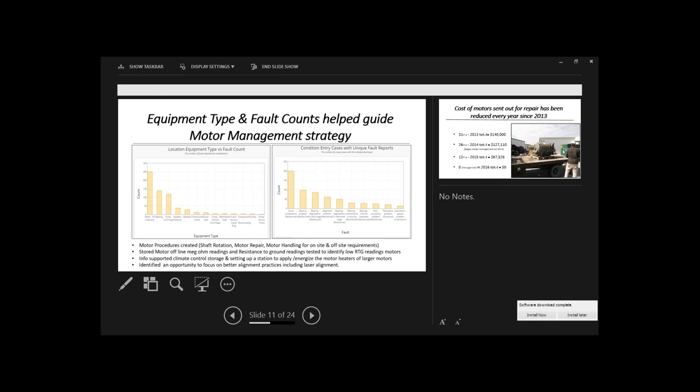In addition to that, he's gone a step further and he does a PM on those spare motors to make sure they're rotated on the frequency, stored properly, and kept clean and dry and all that sort of thing. Some of the most unreliable plants and some plants I've been in are in the storeroom. So the storeroom procedures are very critical. On this particular slide, it's just showing the count of equipment faults. And you see the motors are the highest fault with almost 250 condition problems that they found over the two-and-a-half-year period. The bearings, the centrifugal pumps, gearboxes, and so forth are considerably less. So motors are definitely their high failure item in this particular plant.